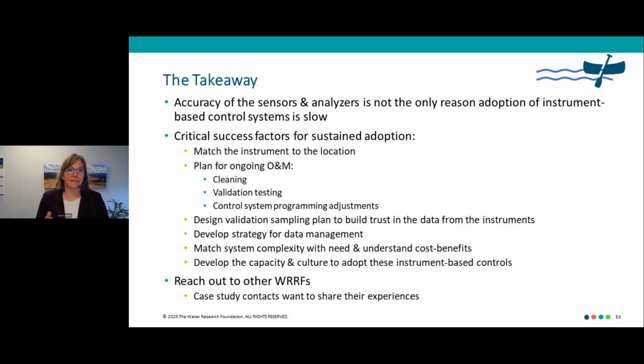So we've identified these critical success factors, and this is based on all of the feedback that we received through the utility surveys, through the case studies, and our own experiences working with these types of systems. And it's really making sure that you're matching your instrument to the location, planning for ongoing O&M, making sure that you've got plans for cleaning and validation testing, and adjustments to your control system that will need to be made either seasonally or as your influent characteristics change.